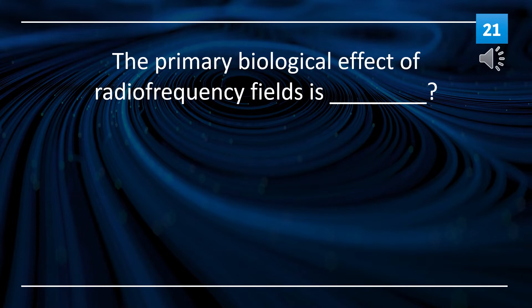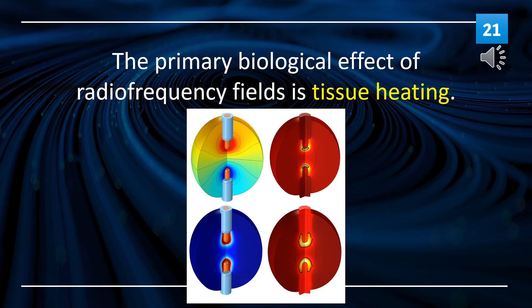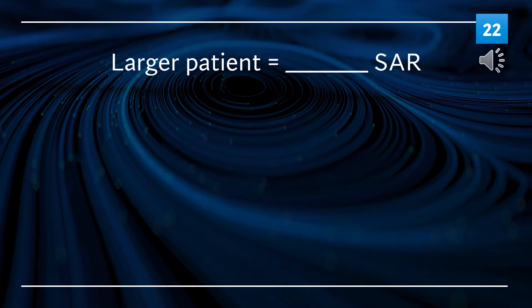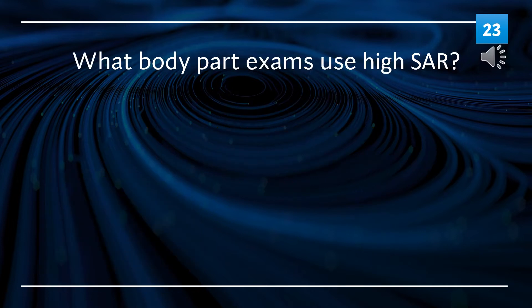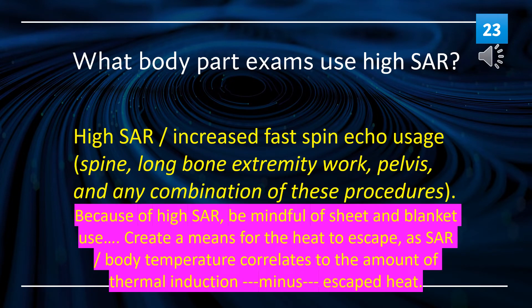The primary biological effect of radio frequency fields is tissue heating. A larger patient equals increased SAR. High SAR body part exams include fast spin echo usage in spine, long bone extremity work, pelvis, and any combination of these procedures. Be mindful of sheet and blanket use when scanning patients, as heat must have a way to escape, since SAR and body temperature correlate to the amount of thermal induction.